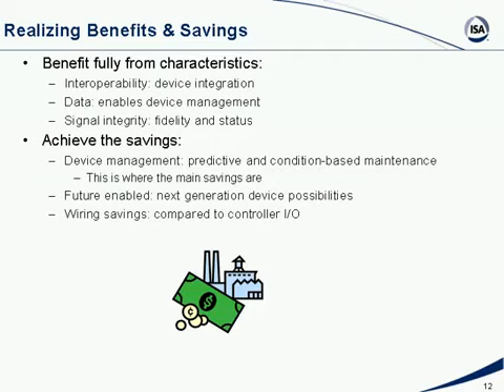Fieldbus results in higher quality, basically by eliminating sources of variability. With Fieldbus devices, I can detect wear and tear in valves, for example, and detect poorly tuned devices. Since I can detect this, I can eliminate it. Reduced process variability really means higher quality, higher yield, and it allows me to push my set points closer to the optimum, so I also get higher throughput for my plant.